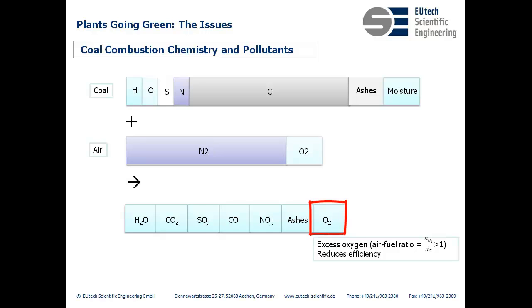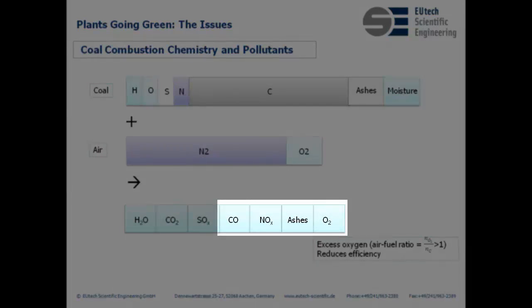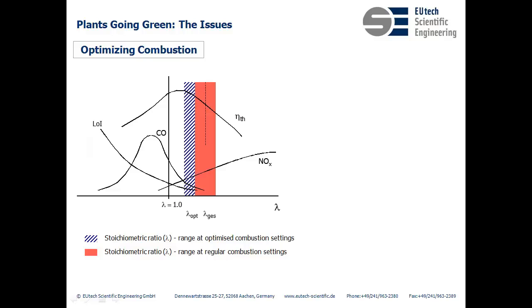And finally, excess oxygen. This is not a product per se, but leftover source material. Excess oxygen can lead to excess pollutants and is associated with reduced efficiency. So there is an attempt to reduce the air-fuel ratio — the ratio between oxygen and carbon. Sulfur oxides generally cannot be directly improved by optimization of combustion, but via other mechanisms. So for the optimizer we're talking about today, the focus will be on the remaining four, as commissioned by the coal power plant: carbon monoxide, nitrogen oxides, ashes, and oxygen. Also, by optimizing the combustion process by reducing excess oxygen, the levels of carbon monoxide are also reduced.